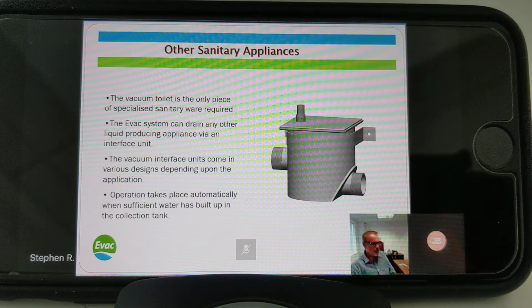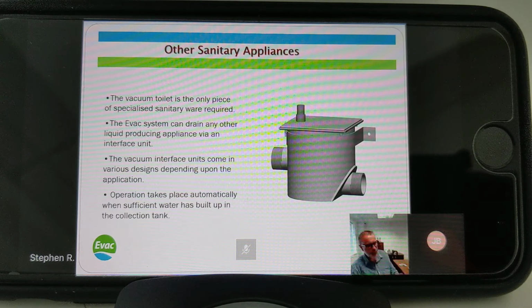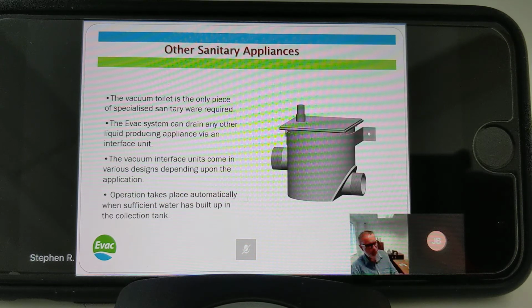As water flows into the box through the inlet that you can see on the left-hand side, the higher one, eventually there'll be enough water in that box which will make that ball become buoyant. The buoyancy will overcome the power of the vacuum, and literally the water is then just drawn out under vacuum and the ball sits down again. So very clever in its design, very simple in its operation. And I think it's key that you understand that it doesn't have to be a real Heath Robinson with all sorts of valves. The appliance unit there, which we call the ball in the box, is as simple as it gets.